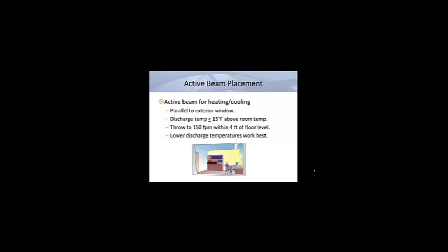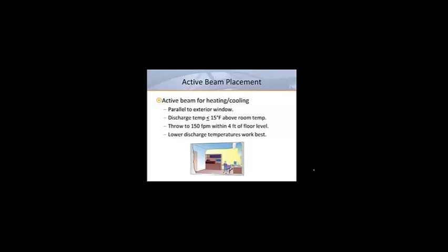When active beams are being used for heating and cooling, they should be placed parallel to any exterior glass. Since they'll be used for heating, it's important that we follow the same rules that would apply to any conventional overhead heating application. Per ASHRAE, we never want discharge temperatures to be more than 15 degrees higher than the desired room temperature. In order to ensure that we deliver ventilation air to the breathing zone, we want to make sure that our throw to 150 feet per minute is within 4 feet of the floor. In order to achieve good coverage on the glass, we know that lower discharge temperatures always work best.